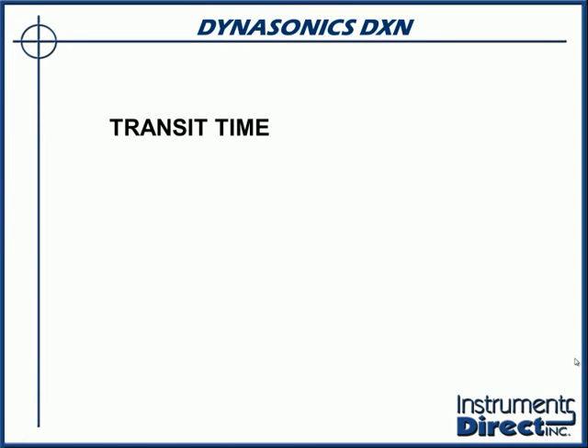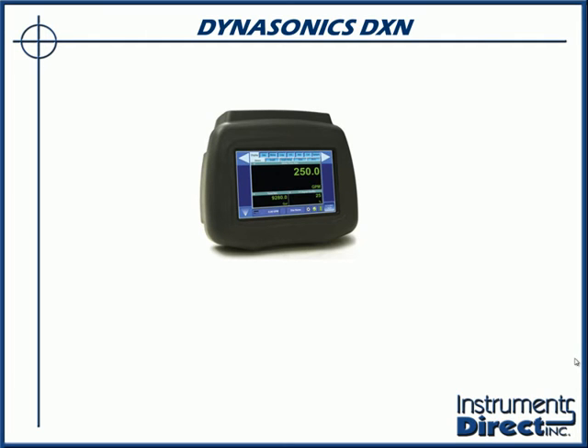What do you get when you mix a transit time meter with a Doppler meter and a computer tablet, and put them all together? You get a hybrid of an ultrasonic transit time Doppler flow meter. Welcome to the DXN. Finally, something completely different in the world of ultrasonic flow meters. This technology is unique in that it can monitor closed full pipe applications of ultra pure liquid, regular water, sewage, and sludge with heavy solids, all in one box.